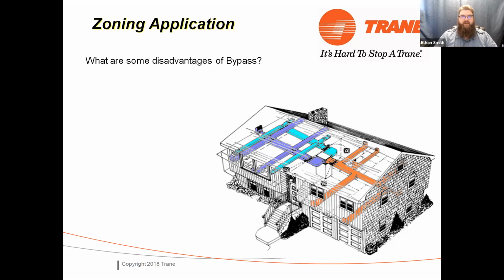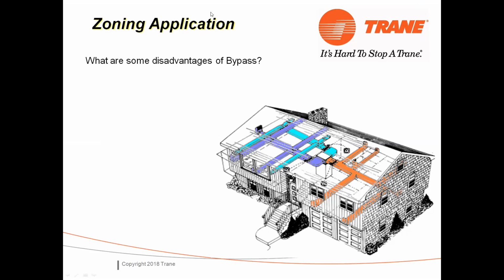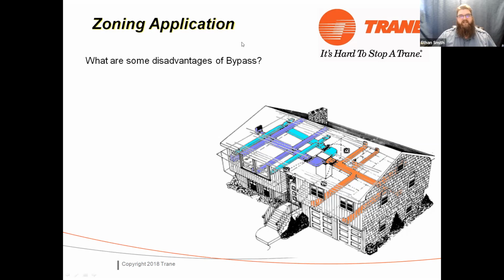Has anybody ever seen a barometric bypass damper applied to a variable speed blower motor? I don't even know what that is. Okay, this is where we have a blower motor that is sensitive to static pressure. So it's going to hit its airflow target based on how much wattage it consumes. And a bypass damper will actually mess with that motor really badly. I have seen zoning systems with variable speed blowers that eat a blower motor a year because it just wears the motor out. So could you do a modulating damper in there as like a floating zone? If there's a lot of hysteresis in that modulating damper, meaning it goes very slowly and it's not responding to static pressure, sometimes you can get away with that with a variable speed blower.